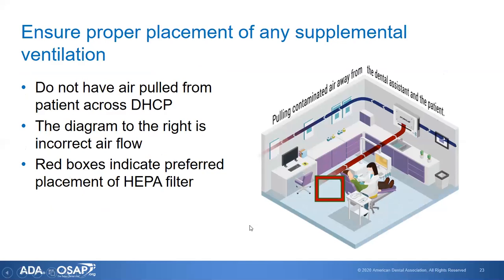This diagram shows one way to place a ventilation system. In this example — I've placed a red box there — you can see the air is drawn across the patient, past the dental assistant, and into the ventilation system on the wall. That is the improper way to create airflow in the office. You want airflow to go from clean to contaminated, not the other way around.